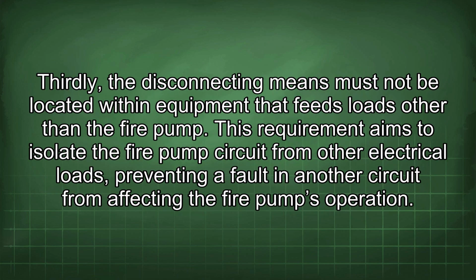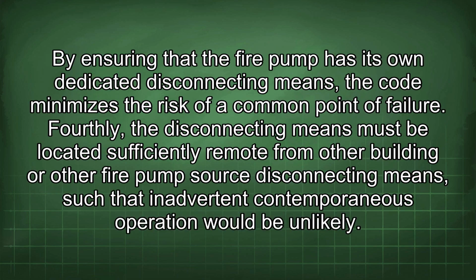Thirdly, the disconnecting means must not be located within equipment that feeds loads other than the fire pump. This requirement aims to isolate the fire pump circuit from other electrical loads, preventing a fault in another circuit from affecting the fire pump's operation. By ensuring that the fire pump has its own dedicated disconnecting means, the code minimizes the risk of a common point of failure.